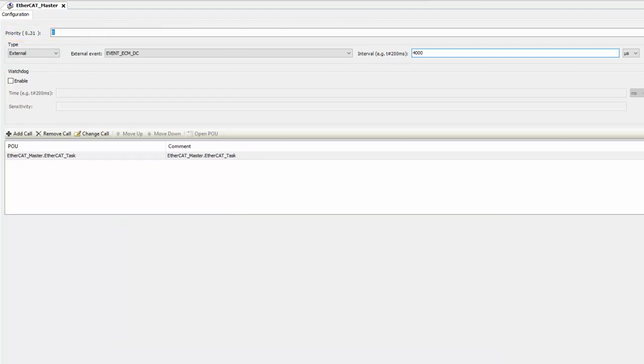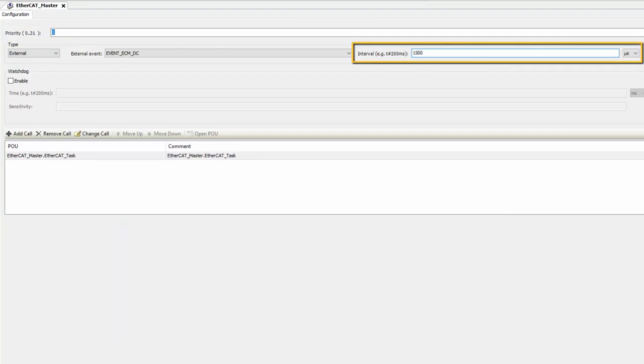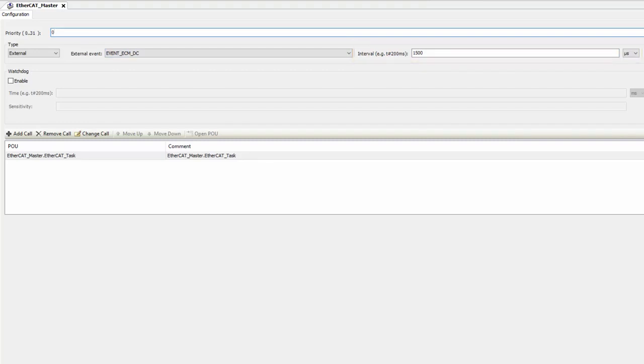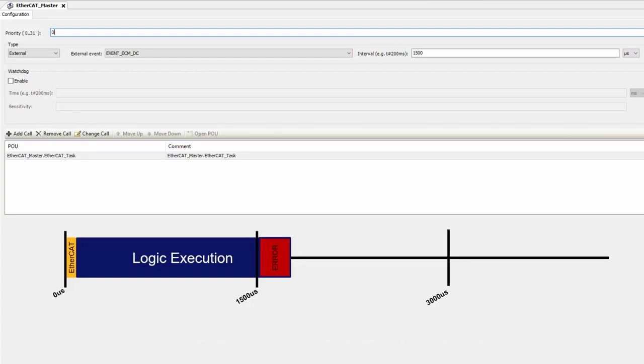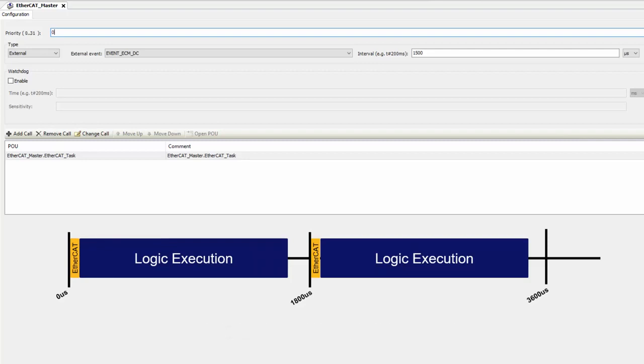This task is set up to run at every 4000 microseconds or every four milliseconds by default. We can go ahead and change that to 1500 microseconds, but users should be careful. The more extensive the programs that are put under this task, the longer that task will take to execute.